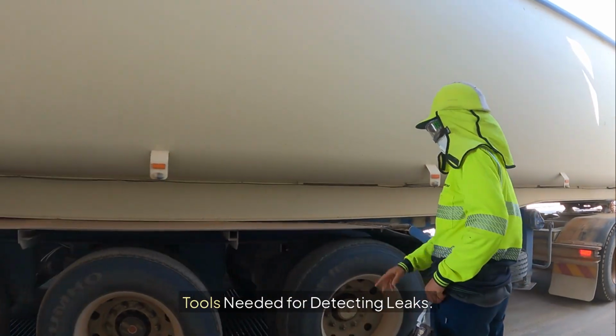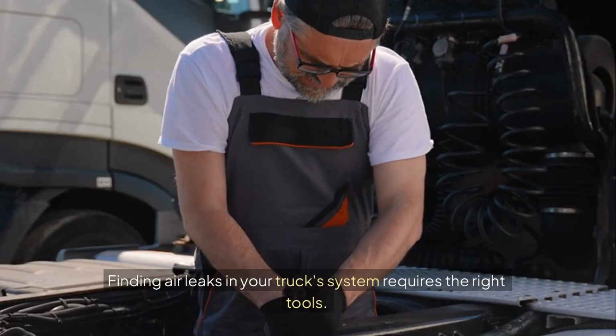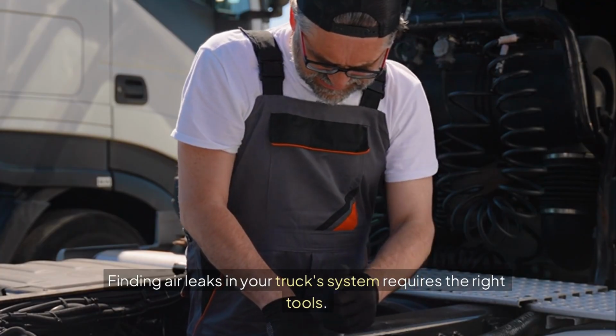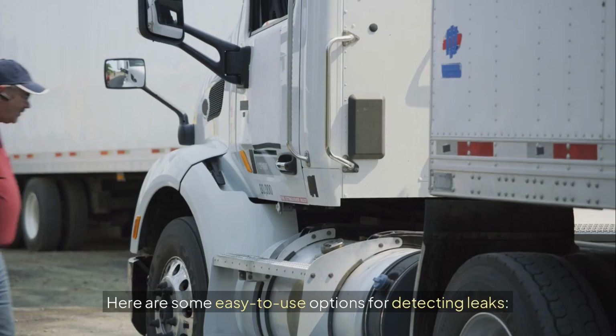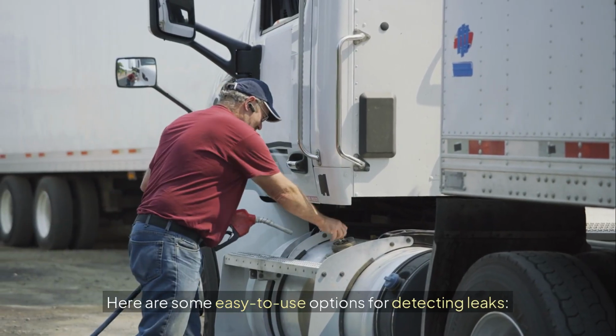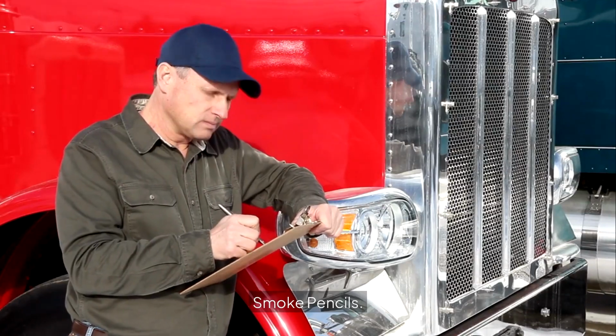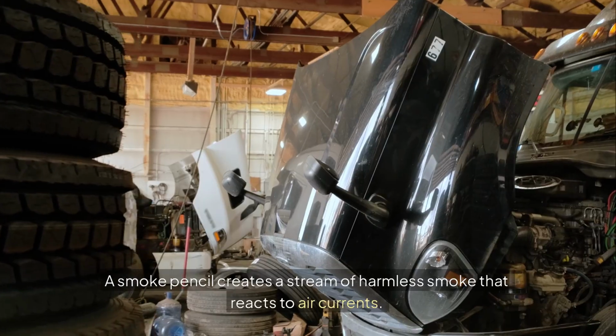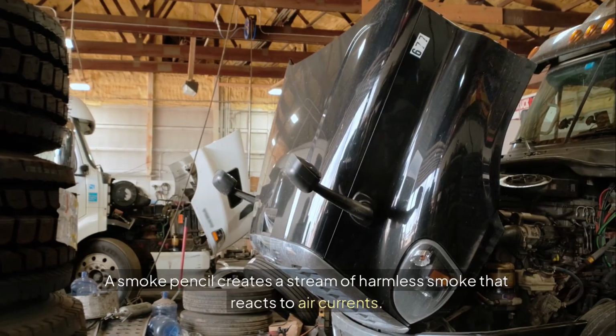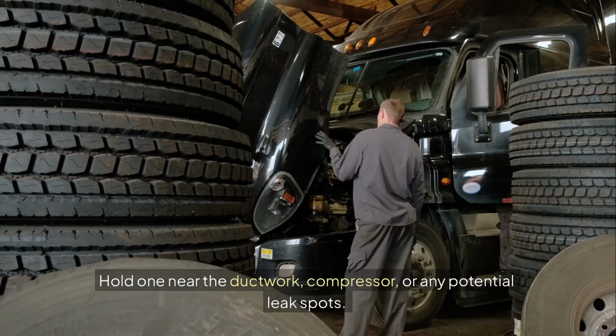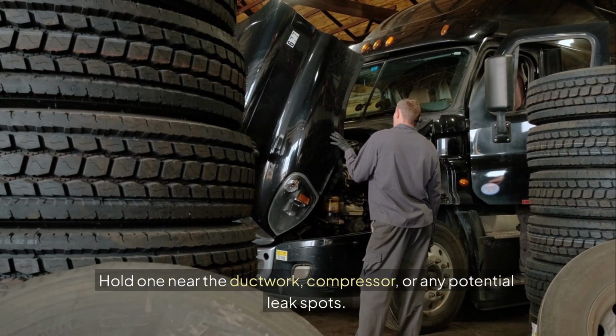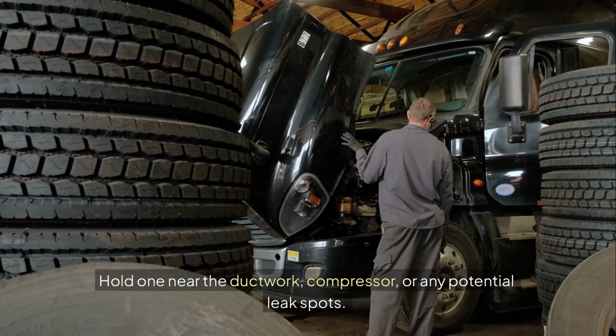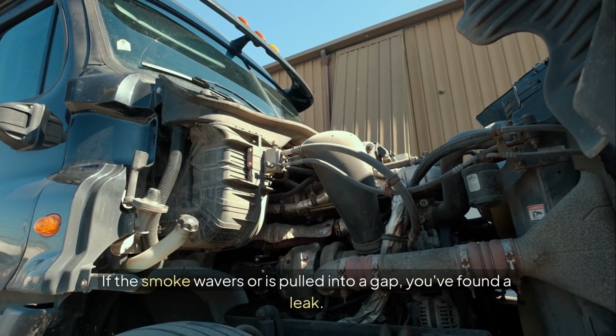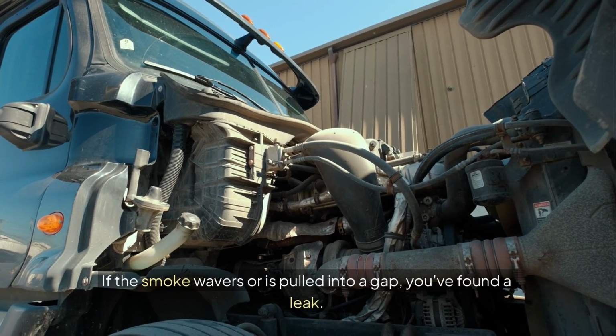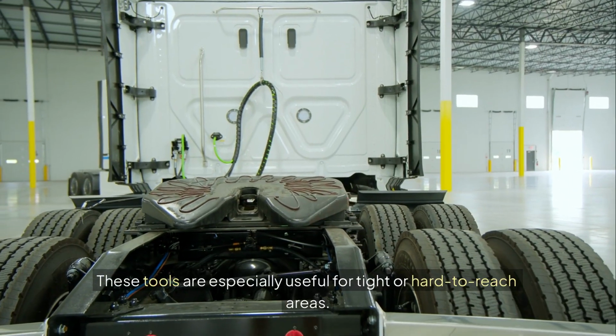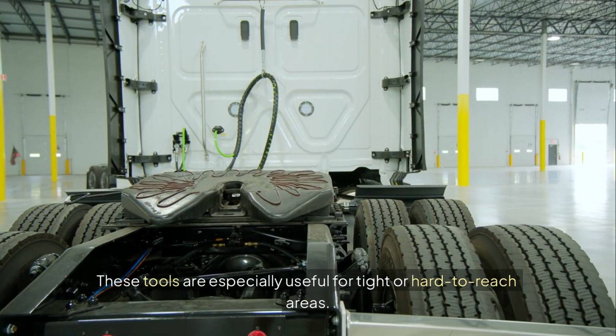Tools needed for detecting leaks. Finding air leaks in your truck system requires the right tools. Here are some easy-to-use options for detecting leaks. Smoke pencils. A smoke pencil creates a stream of harmless smoke that reacts to air currents. Hold one near the ductwork, compressor, or any potential leak spots. If the smoke wavers or is pulled into a gap, you've found a leak. These tools are especially useful for tight or hard-to-reach areas.